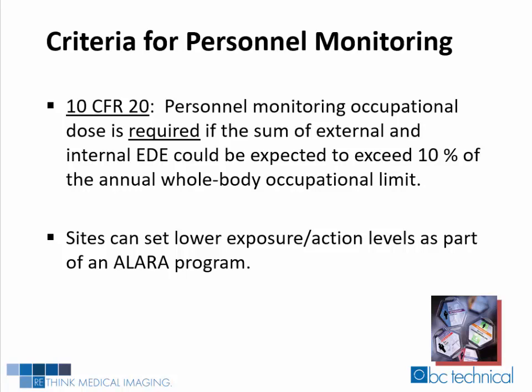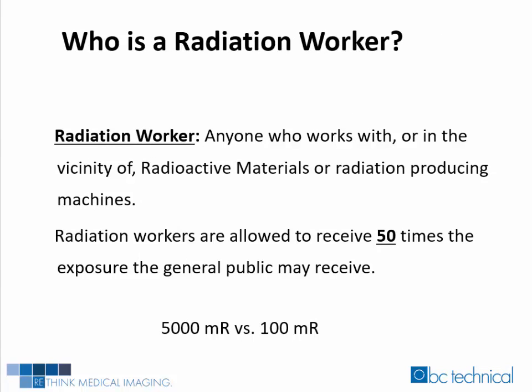Contact your RSO if you have any questions regarding the exposure limits at your facility. A radiation worker, by definition, is anyone who works with, or in the vicinity of, radioactive materials or radiation-producing machines. Radiation workers are allowed by regulation to receive 50 times the exposure that the general public may receive. Therefore, a radiation worker is allowed to receive 5,000 millirems per year. The general public is only allowed to receive 100 millirems per year.